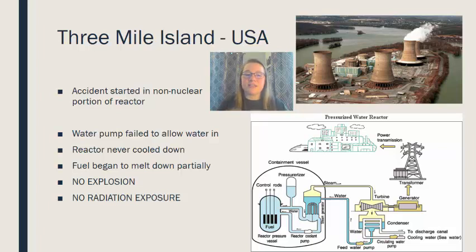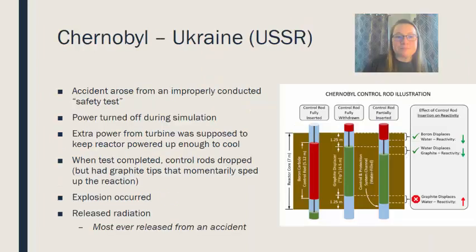What happened here is a water pump that helps with the cooling system failed and a partial meltdown occurred in that fuel. Again, the operators were able to observe this really quickly, they shut things down very quickly, and there was no major accident that happened here. So this is pretty negligible. It's kind of a bit of a stretch to call this an accident. It was just more of a whoops, something went wrong, but we fixed it right away.